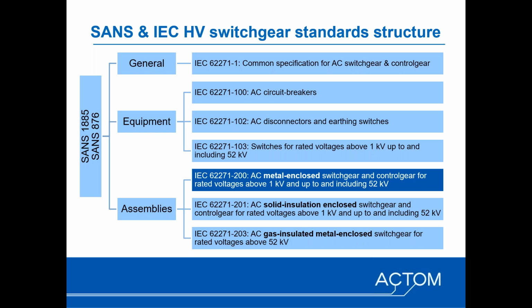And then there's some front-end SANS standards, which cover preferred requirements for the South African industry, standards that were previously NRS standards and then were adopted as SANS standards and effectively extended to a broader audience. Examples of that would be SANS 1885, which covers metal enclosed switchgear, so effectively a front-end standard to -200. And then, of course, that refers to some other important standards, such as SANS 876, which covers the insulation requirements for medium voltage conductors and cable terminations.